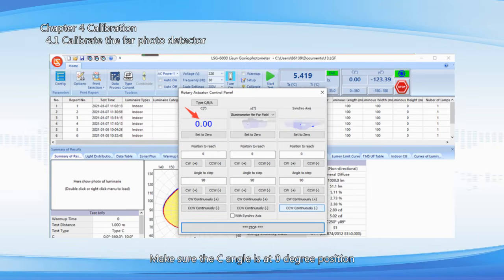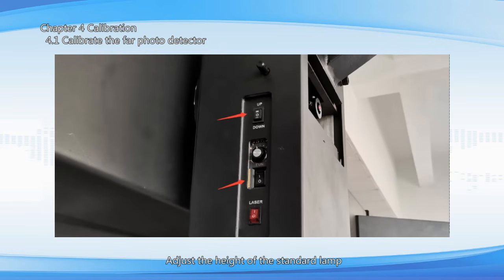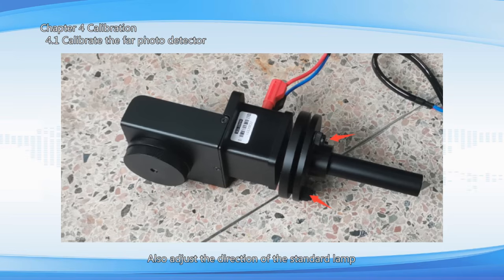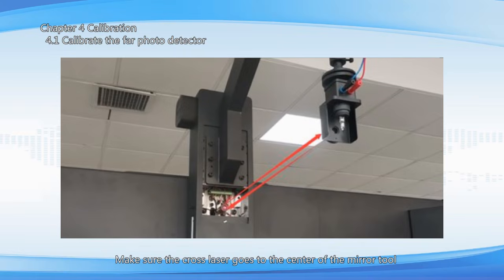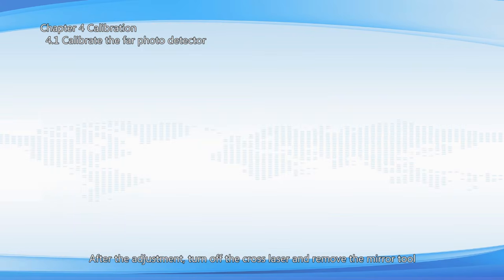Make sure the C angle is at 0° position. Adjust the height of the standard lamp. Also adjust the direction of the standard lamp. Make sure the cross laser goes to the center of the mirror tool and the reflected horizontal laser and vertical laser coincident with the original horizontal and vertical laser. After the adjustment, turn off the cross laser and remove the mirror tool.